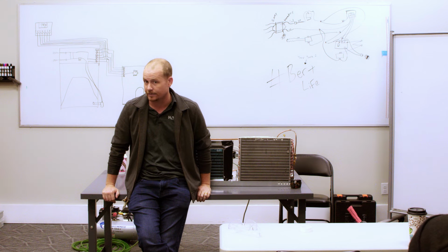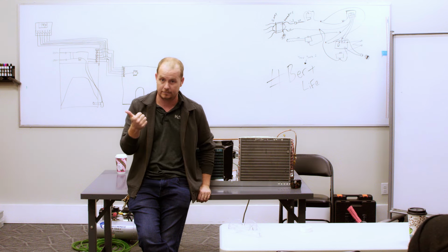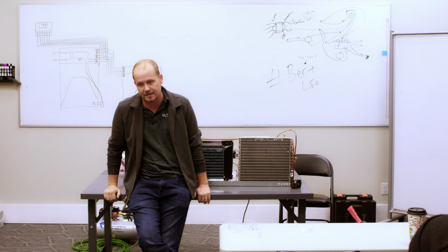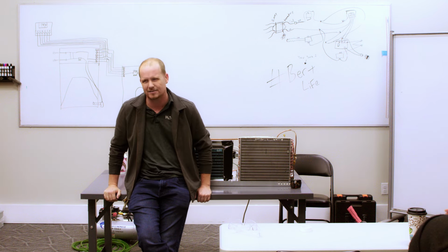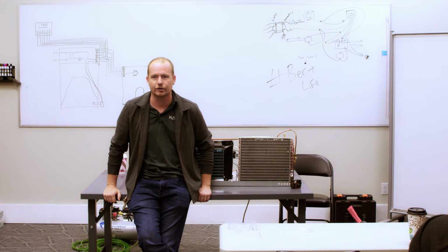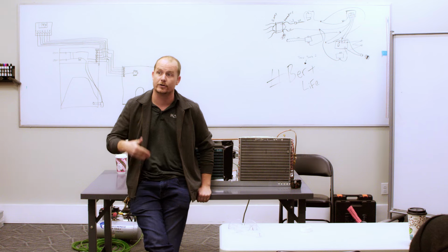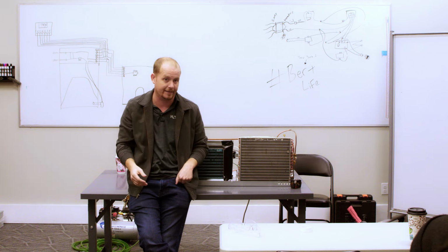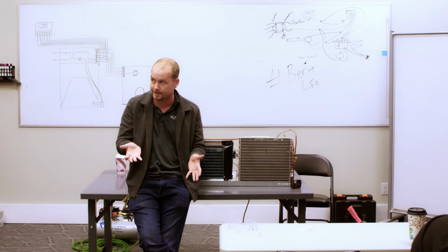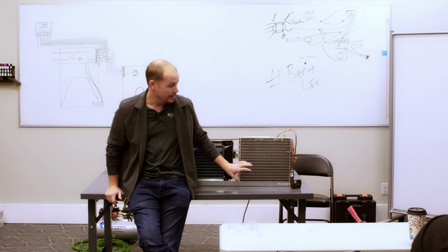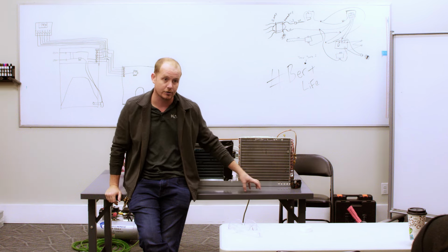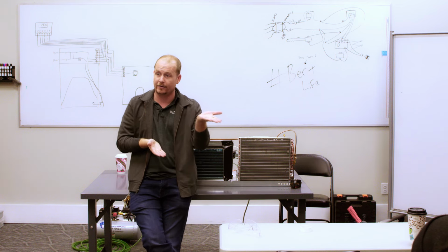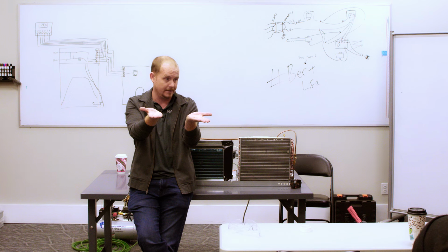And the combination of knowing our outdoor temperature, so this drives diagnosticians crazy when a new guy calls you, man, this head pressure seems high, what's your outdoor temperature? Well, it's been a while since I checked it. Or I think it's probably about 85. It's like, give us a good, correct temperature measured in the shade where it's not affected by the coil temperature or the sunlight or anything like that, so that we have something to compare to, because we need that. Then we need your subcooling, and then we also want your liquid temperature, because we're going to compare the liquid temperature to the outdoor temperature.